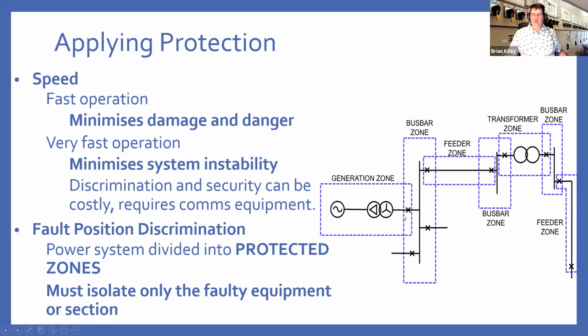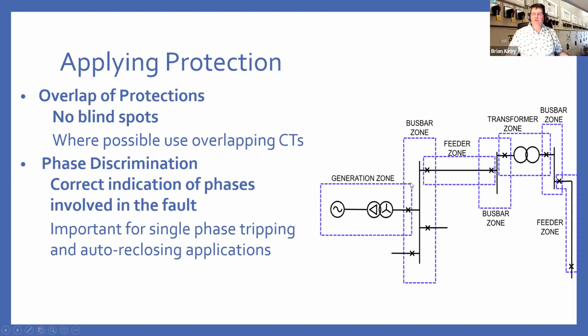But if you detect a fault in your zone of operation, you only want to isolate the zone that is faulted. Obviously, if there's a fault in the generation zone and you turn the generation off, the rest of the network by default will go off because you've lost your source. But if you get a fault, say, on this feeder here, and you have other feeders going off elsewhere, you don't want to lose those supplies. As I mentioned, overlaps, we don't want any blind spots. And we also want to look at phase discrimination, although in the UK, National Grid generally operates on a three-phase tripping policy.